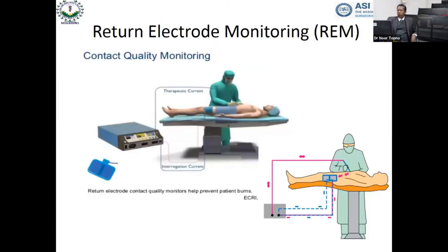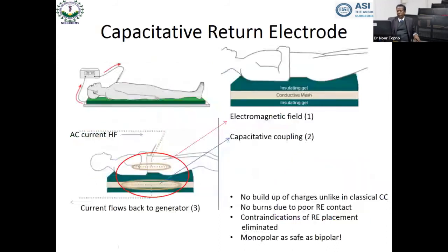Now, this return electrode monitoring is something that is very interesting. Here, this is in 2 parts, the return electrode. So basically between these 2 you have a circuit. So whenever there is any loss of contact between this and this, it will not allow the machine to operate. And that's how it prevents electrode burn in the return area.